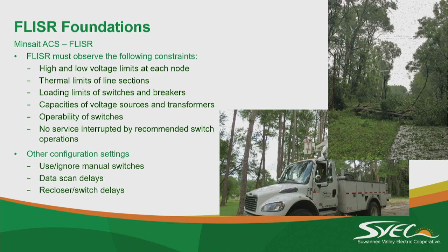We send a signal out, and FLISR will not advance to the next step until it sees the device report back closed or open. I think that's also in the switch plan. It may send a command, and it waits. Oh, status came back. It does say open and closed. So you have to map all that into FLISR. It needs to know the command to open and close, the control point, but there's also the status point. So it will not advance. If one doesn't come back and say it closed in or didn't open, it stops.